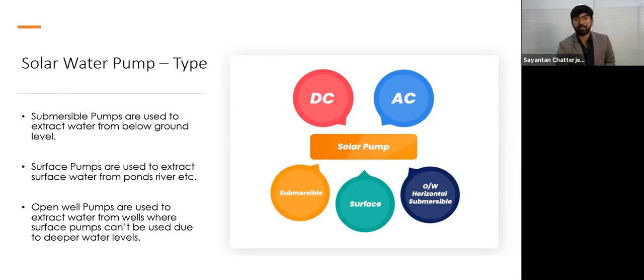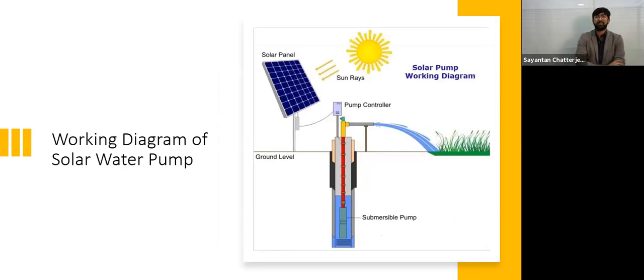Now we will go to the basic block diagram of a solar pumping system. Here we have considered a submersible pump lowered into the underground level, and we are using solar panels connected in a string to generate the desired voltage and current. The motor runs optimally via a pump controller - a VFD, variable frequency drive. By changing the frequency, we can control the speed of the motor based on available solar power. That VFD has an MPPT, maximum power point tracker, inside, which tracks the maximum power from the solar panel and drives the motor in the most optimistic way.